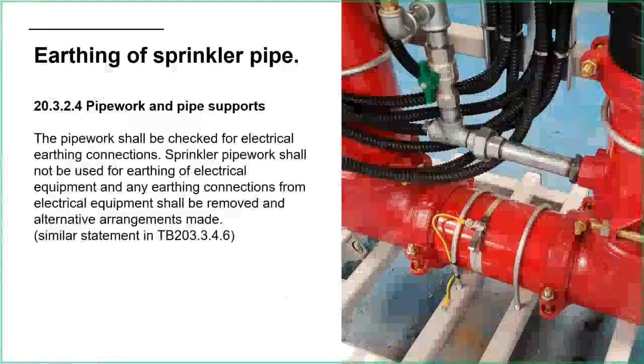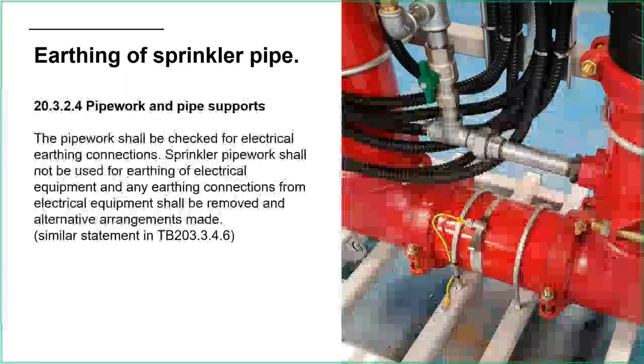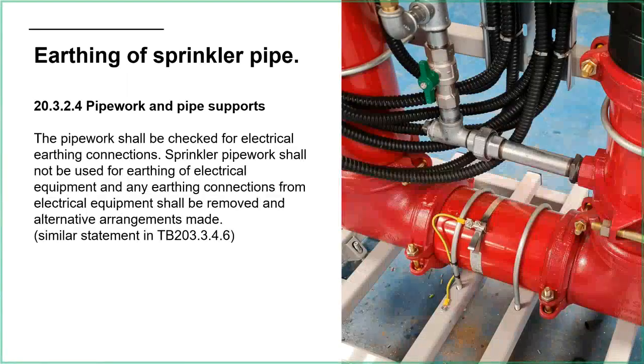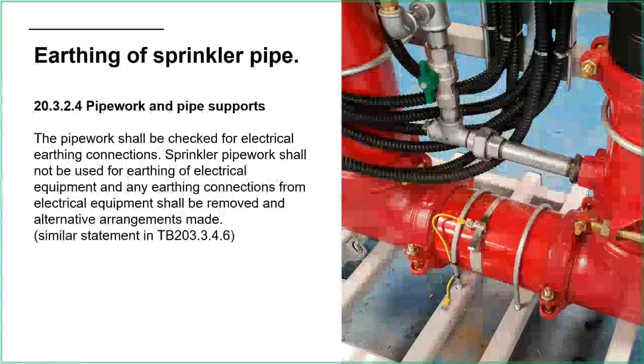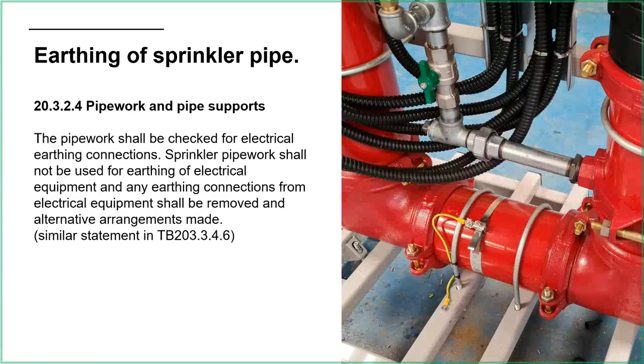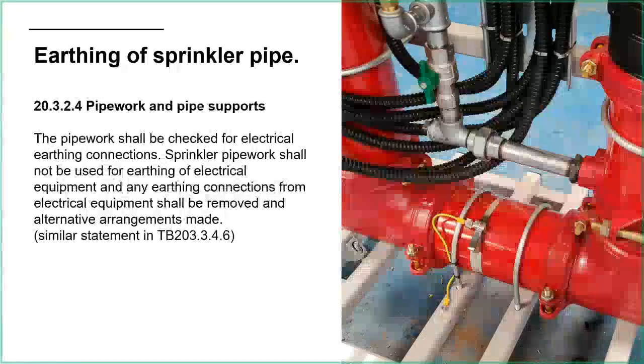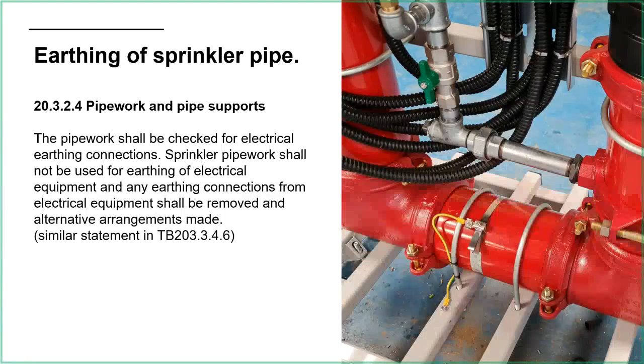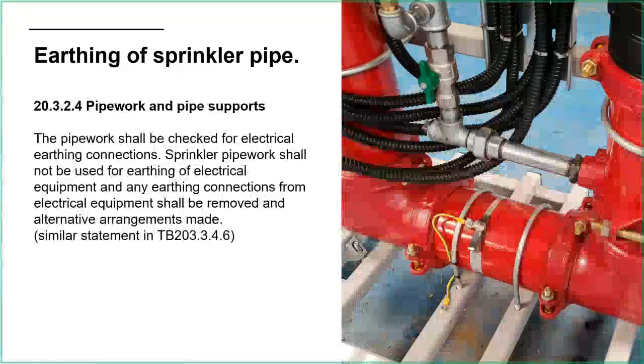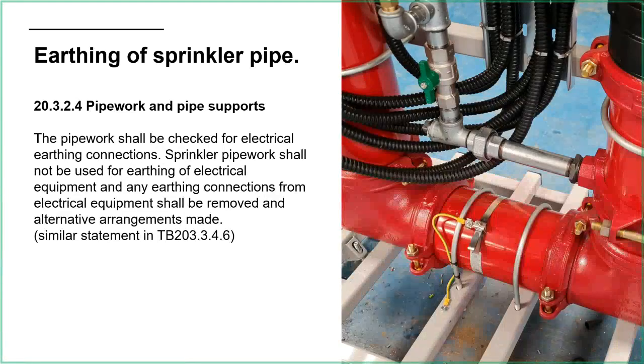Earthing is another niche topic in terms of pipe, same as with copper pipes. Whenever we've got a long line of pipework, we want to allow some earthing or bonding. I'm not an electrical guy, but I believe the idea is that if a live wire touches some of this metal pipework, the danger is that all of that metal pipework becomes live. Whereas if we earth it, that causes the electrical circuit to trip, so we know there's a problem and can find and fix it. Without earthing, all of that pipe could become live, and anyone who touches it would come into contact with the electrical supply. So yes, we do have earthing of sprinkler pipework.